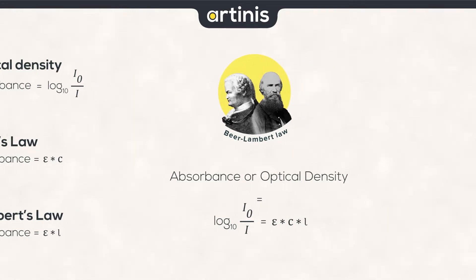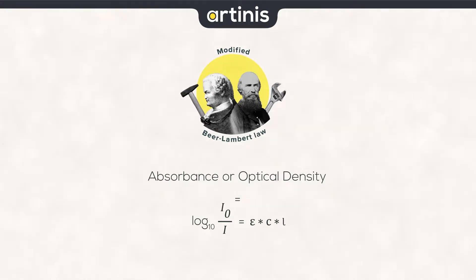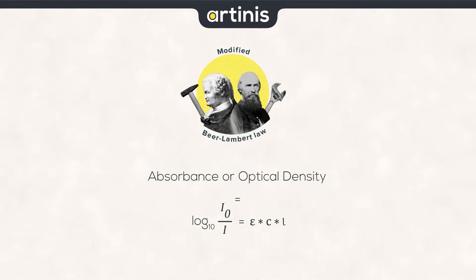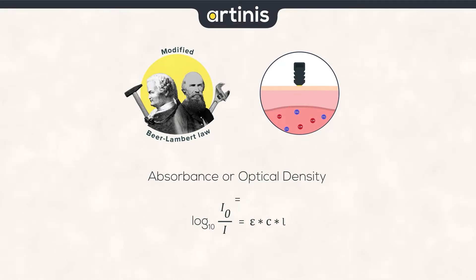In near-infrared spectroscopy, we use a modified version of this formula, the modified Beer-Lambert law, to estimate concentration changes from physical properties. Why does it need to be modified? Because the regular Beer-Lambert law assumes that light does not scatter in the medium it is measuring, but in biological tissue, light does scatter.